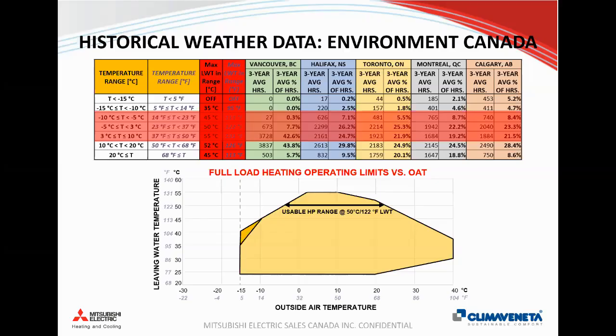And really, the way you can have the highest efficiencies and a broader operating range with air-to-water heat pumps means that you want to design for the lowest water temperature that is feasible for your design, so that you can have a broader range of time that you can operate the machine and still have a high enough supply temperature that you can meet the heat load in the spaces that you require.